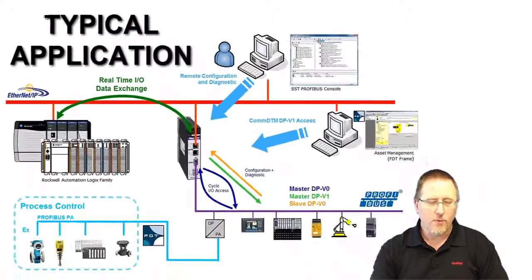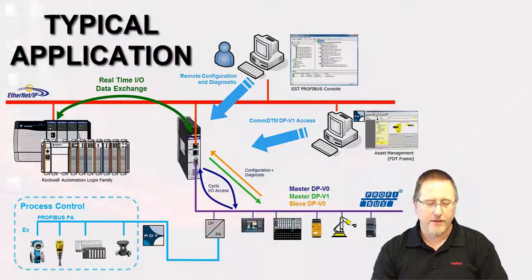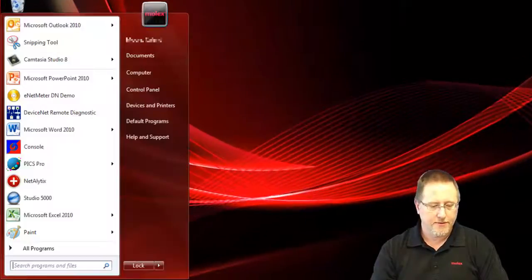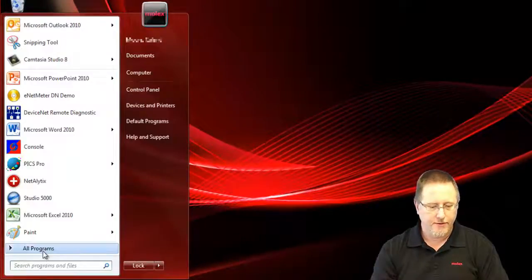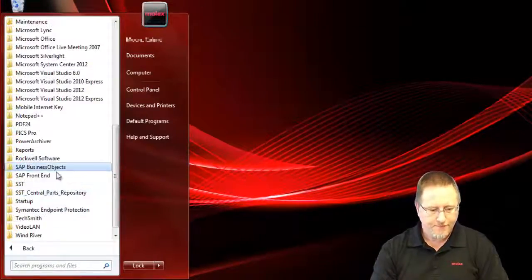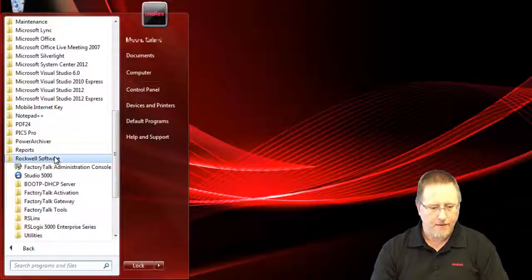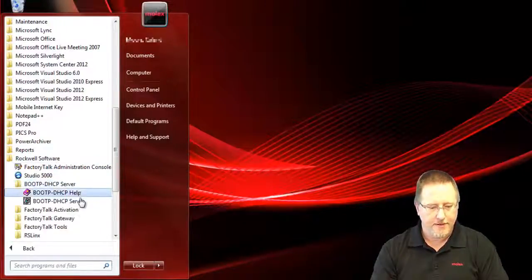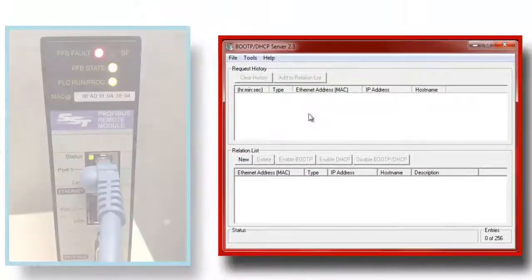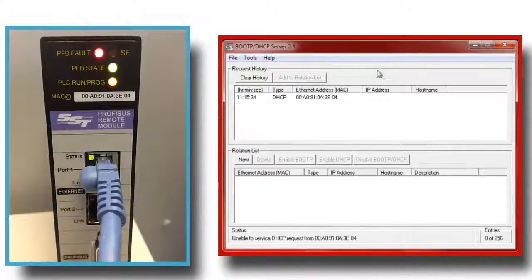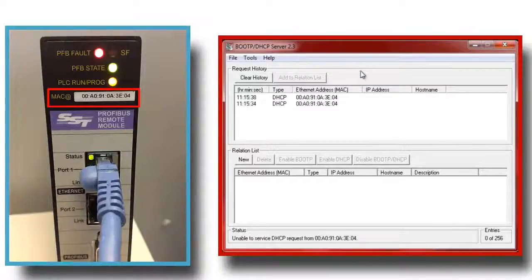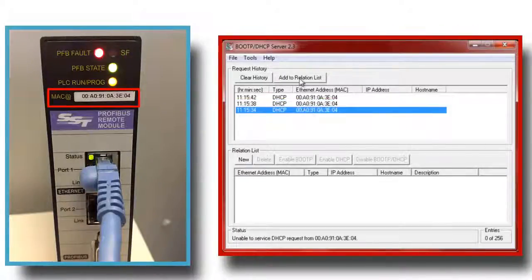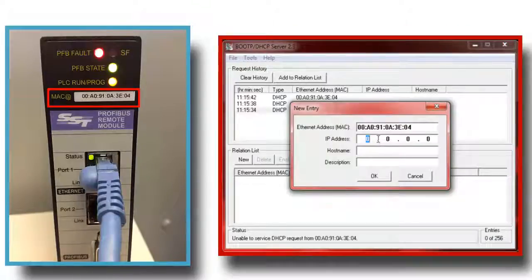When you first get the module it will be set up for DHCP, so we'll go into the Rockwell software and select the BootP DHCP server. On the front of the module is the MAC address and we see there it's showing up 3E04, so we select that and assign an IP address.